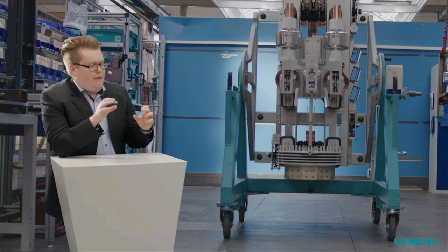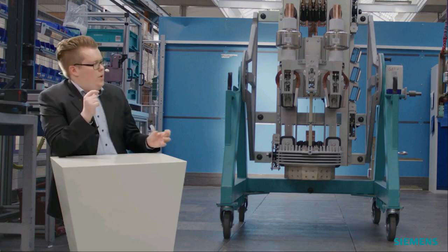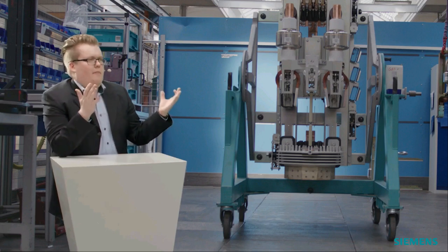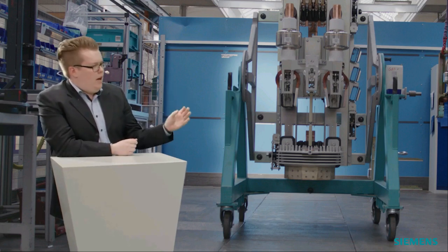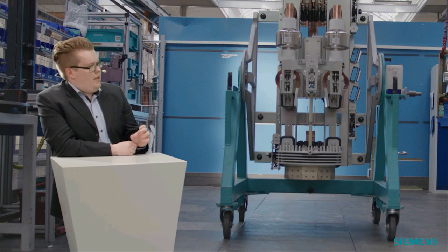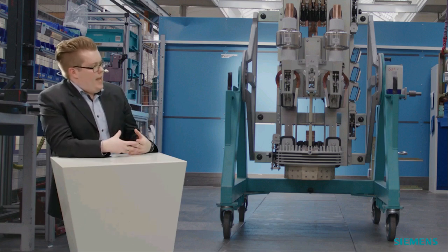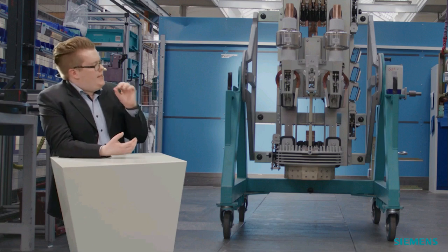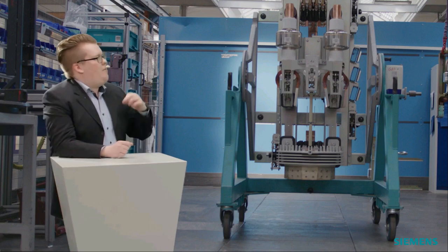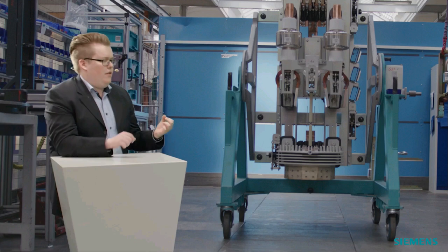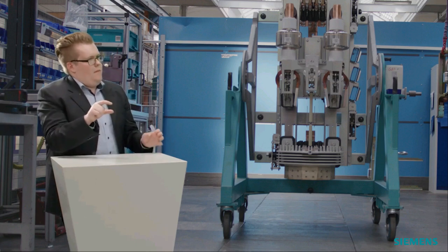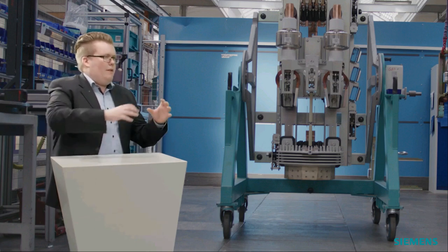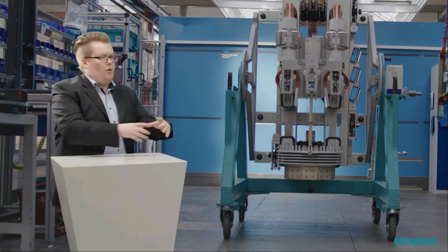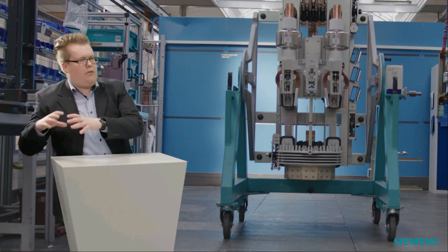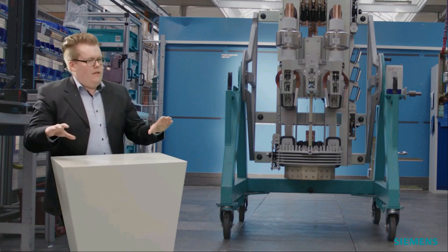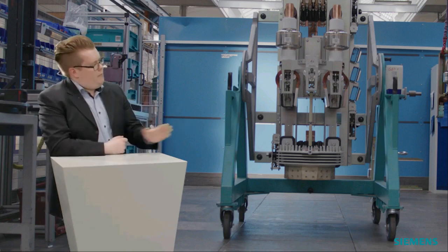So if we have a multiple generation network and we have, for example, four generators all having only 3 MVA of power, this will be a total power of 12 MVA. So the IEC IEEE standard is actually not applicable for the small amount of power. This is actually the same as having one big generator for 12 MVA or four small generators with 3 MVA. These two powers are not covered by the standard.